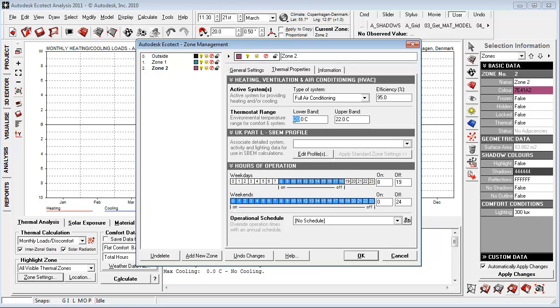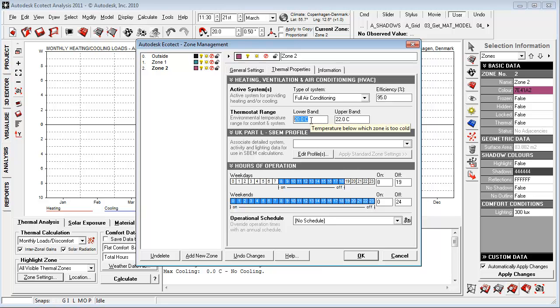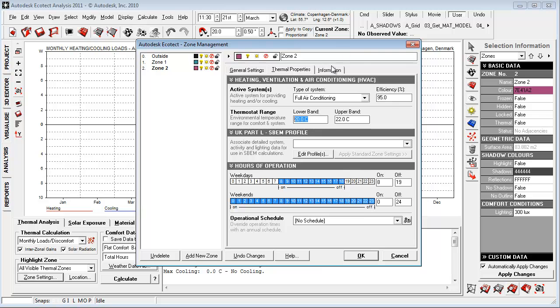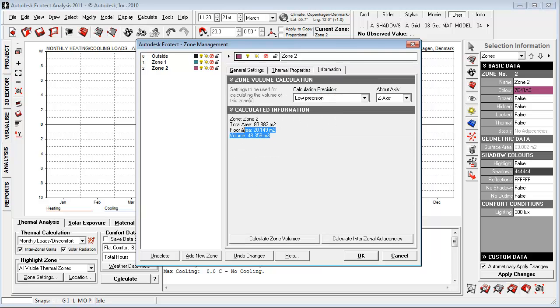If we choose full air condition, if the temperature drops because of cyclic variations, it will try to use energy to heat the building if it gets below 20 degrees and to cool the building if it gets above 22. These two can really be used as indicators for what we can manage within the space. Set up the outside variation and check that the total area, floor area, and volume are calculated correctly.